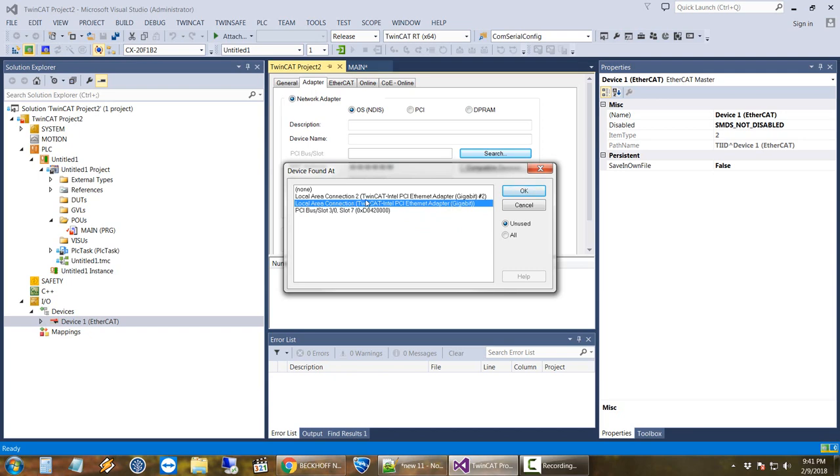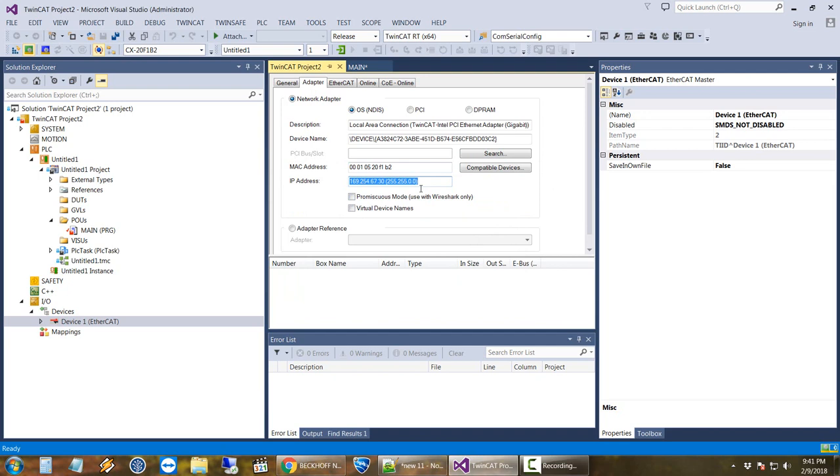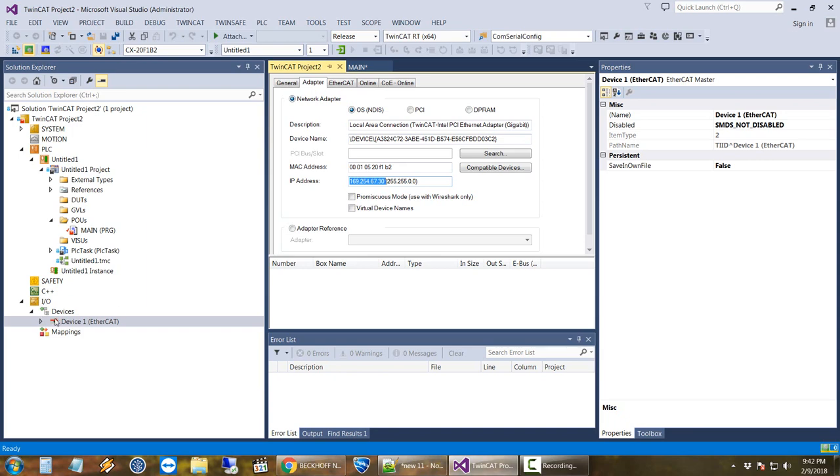One of them called EtherCAT and one of them called LAN or something. And then those names will travel through here just to make it a little clearer when people go back in and debug. But since I didn't rename those, I'm just going to pick one. And you can see what IP address it got. This is a link local address, which basically means it more or less doesn't have an address. It can talk to other link local stuff. But that said, it searched for DHCP and nobody gave it an address. So it's just hanging out. That's what we want because it actually doesn't need an address at all to talk on EtherCAT. And for that matter, you can go and uncheck the TCP/IP stack on the driver. And that'll make sure that nobody really mixes it up for other stuff accidentally. So it's grabbed the MAC address. That's another way to check and make sure you have the right one. But we know we do because the other one, if I were to pick it, would have that 192.168.1.130. And so we don't want that. This is the one we want. We're happy.